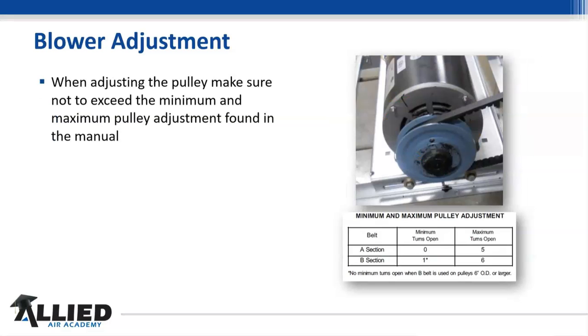But also what we want to be really, really careful of is not to run this pulley, or run that belt, very low in the pulley. If you have to run the belt too high or too low, that's where we really need to look and say, okay, we may not have the right drive kit in here. And the catalog number I talked about last week, if you'll have that number, it's on a white tag on the corner post of the unit. It'd be like an M199 or something of that nature.